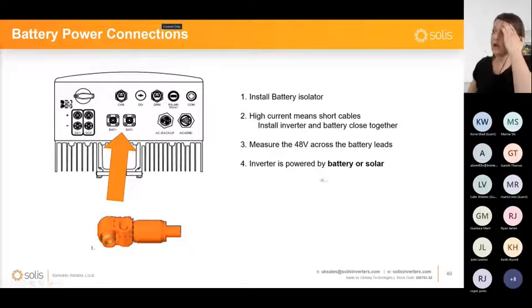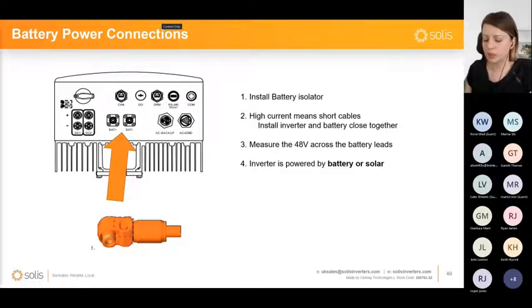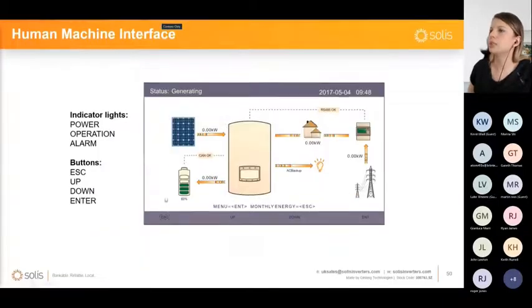Always make sure that you get proper voltage on the battery port. I have to tell you that some of the battery manufacturers, I saw, that actually if there is no load, so no inverter connected to it, you might not find voltage on the battery ports. You'll find voltage only after they get connected, but you're going to be able to see on the inverter screen if the inverter is measuring voltage on those ports, and I'll show you a little bit later.